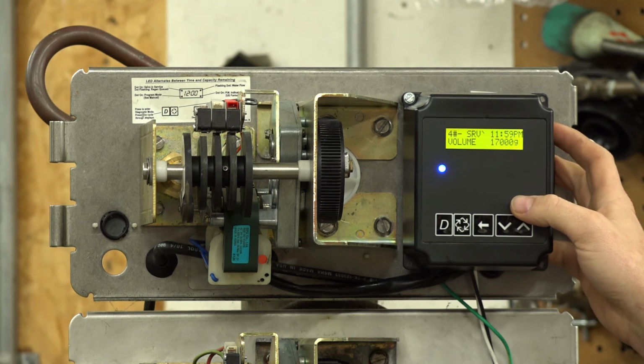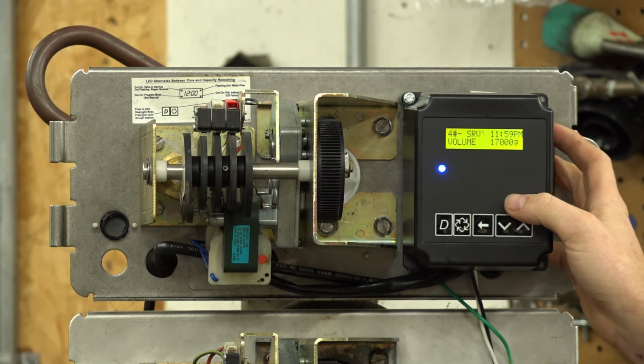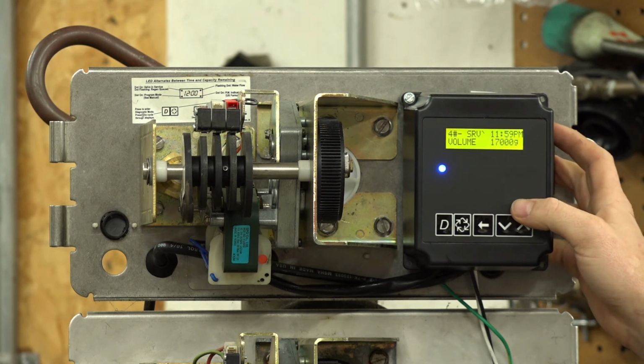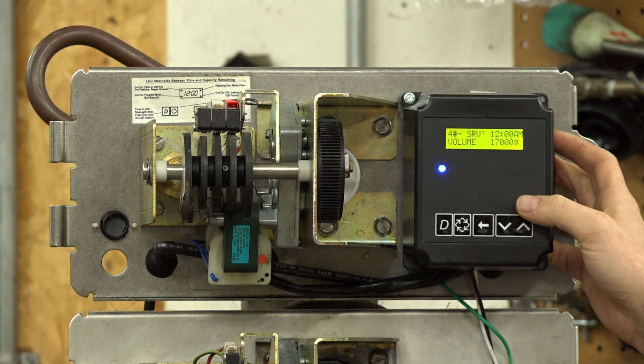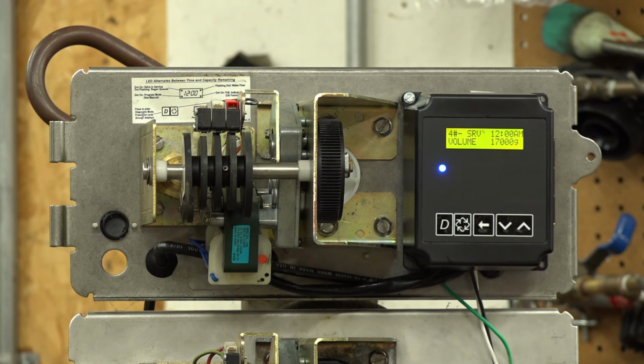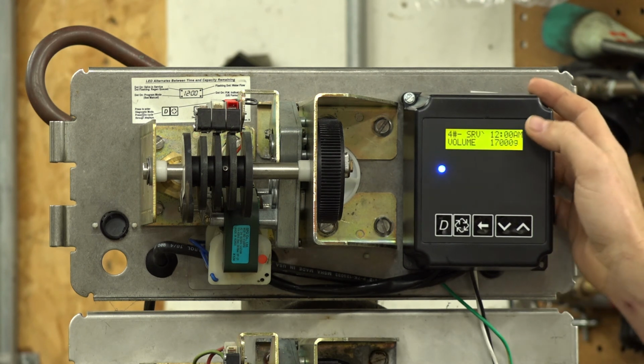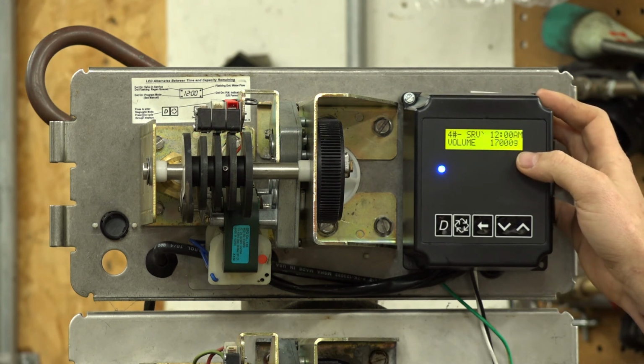Sometimes, if you've got an RGQ, which is a regeneration queued, a lot of times we'll get the call where one's in service, one's got regeneration queued, and nothing's happening. They've got hard water. A lot of times there's a communication issue that's not allowing the one that needs to regen, which is in service, and the other one just stays in standby. And there's usually a communication problem going on at that point. So you're going to want to look for that.